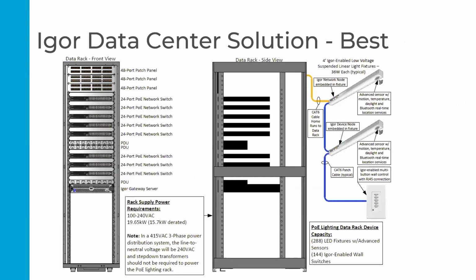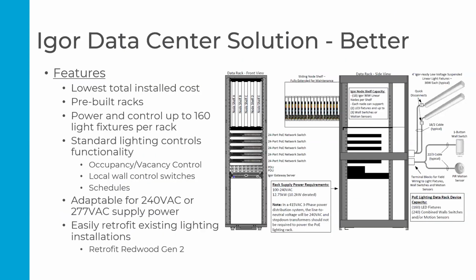Hey, Andrew, so like back on that last slide, are you telling me that the only place you need line voltage is one place, and then everything from the rack downstream is all low voltage? Absolutely. Yep. You're bringing your line voltage really into those PDUs. PDUs are feeding that voltage out to the PoE switches, and then everything after that is either 55 volts DC or less. So very safe, very easy to work with from that point onward.